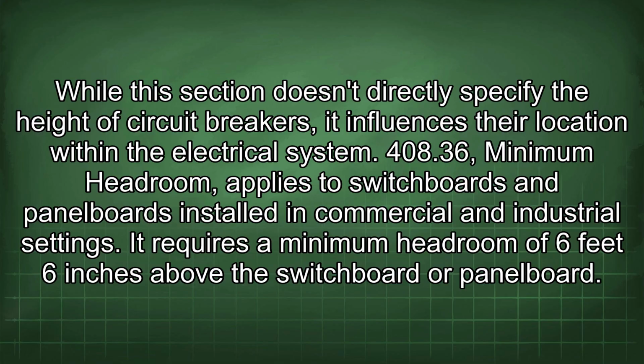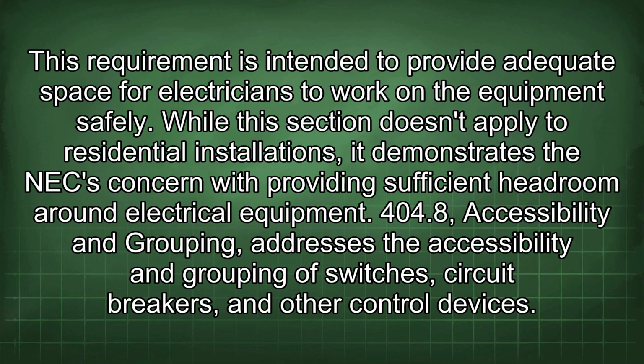408.36 Minimum headroom applies to switchboards and panelboards installed in commercial and industrial settings. It requires a minimum headroom of 6 feet 6 inches above the switchboard or panelboard. This requirement is intended to provide adequate space for electricians to work on the equipment safely. While this section doesn't apply to residential installations, it demonstrates the NEC's concern with providing sufficient headroom around electrical equipment.